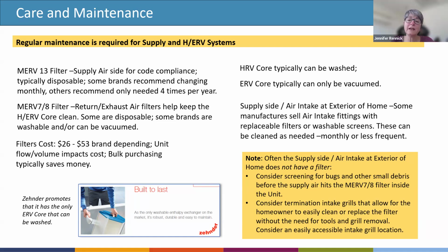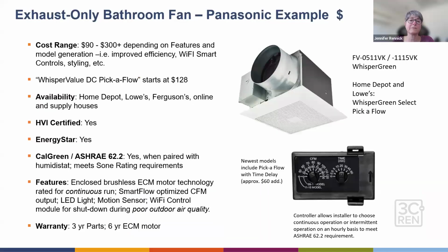Now, when you have an HRV and an ERV, HRV cores typically can be washed once in a while, but the ERV cores, typically you only vacuum them. So it's important to have your clients understand that if they get that system, there is some maintenance that needs to be done. The Zehnder, however, part of why it's maybe more expensive is that it also promotes that its ERV core can be washed, which helps homeowners take care of their systems. And then the last thing is just to think about those terminations, because there are bugs and other things that get into the system.